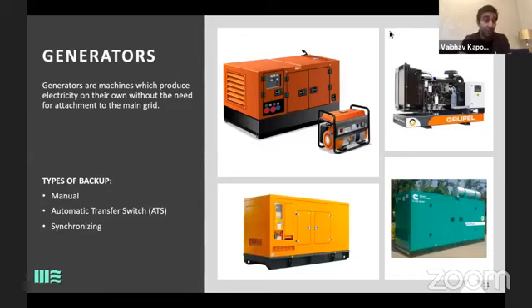Third is the future of gensets. Future in India of gensets. It's already been used abroad for the past 15 or 20 years. In India, there are companies who are working with synchronization. We, as a company, also work with synchronized gensets. So what is synchronization? Synchronization is different from manual and automatic because over here, we don't have any hot backup. We don't have any genset which is running idle. So if two gensets are running synchronized, then automatically they are sharing the load. So no genset is running idle. The more gensets, the more synchronization, the more backups are created on site, and the more reliability.